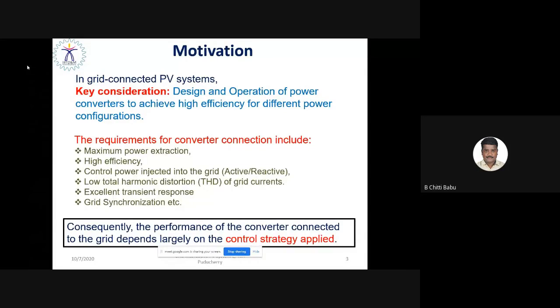In addition, grid synchronization is an important component. With the help of grid synchronization, we are able to integrate such renewable energy sources with the utility grid. So these are the possible requirements for the power converter. And to achieve these requirements, the performance of the converter connected to the grid depends largely on the control strategy that we apply on the grid side converter, or grid connected power converter. It needs to be precisely applied so that we are able to achieve these grid connection requirements.